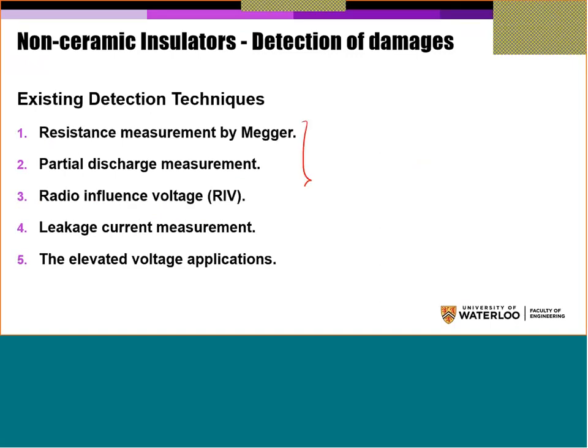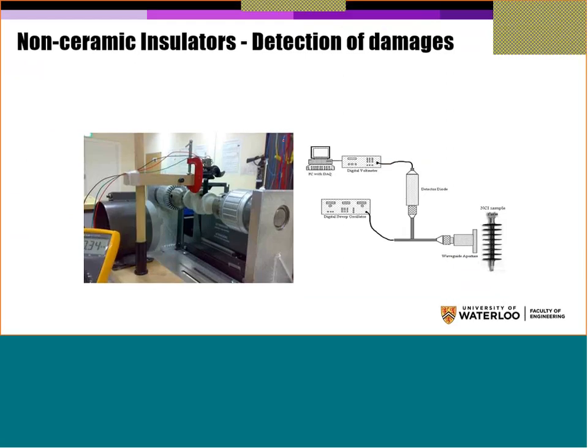They tried to use different techniques to detect those defects, using resistance measurement, partial discharge, radio influence voltage, leakage current, etc. They did not find any technique that is capable of detecting all faults. Some techniques can detect some faults, others can detect other faults, but there is no technique that can detect all the faults.